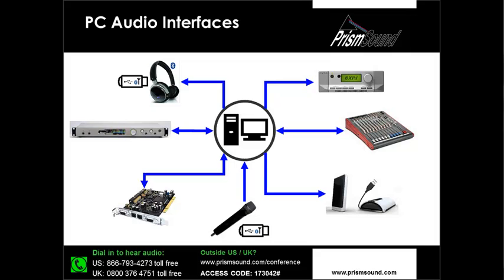And that presents an interesting challenge. Historically, these types of devices would be tested by perhaps generating some WAV files in some third-party software, perhaps recording what's coming in via the USB stream onto some third-party software, and doing some analysis on WAV files offline. So it's a little bit involved, time-consuming, and potentially open to error if you're not 100% confident that your digital audio editing software is doing what you think it ought to be doing.